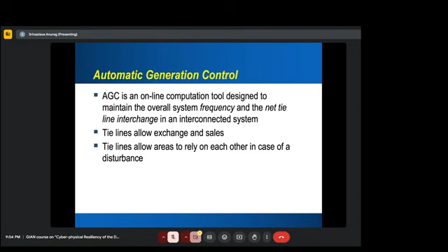So tie line basically allows areas to rely on each other when it's needed, and especially under disturbance, it will automatically increase or decrease the generation. But AGC is a control mechanism, right? So it's a mechanism to increase and decrease the generation, which can also take control commands from the control center, other than the automatic control command.